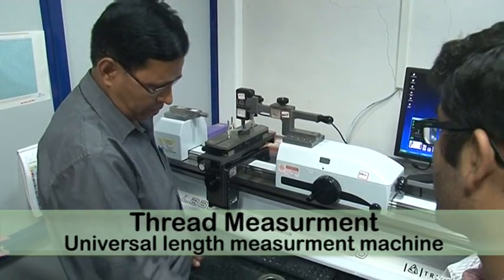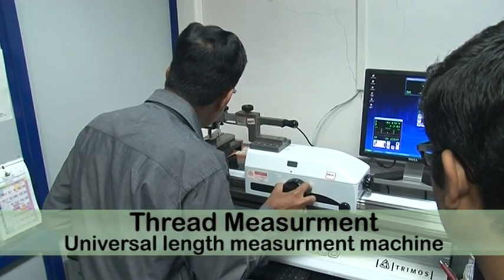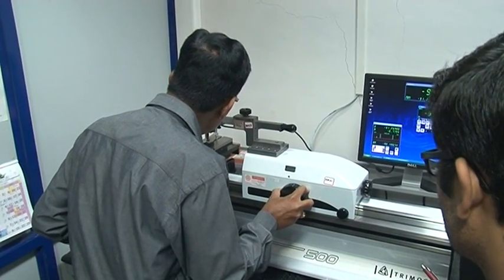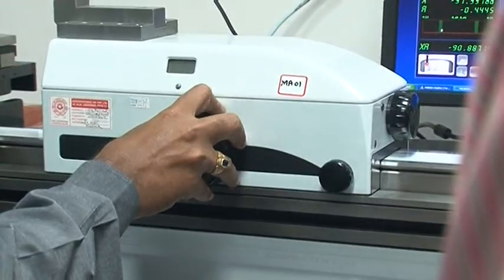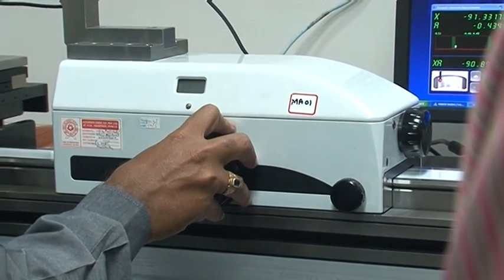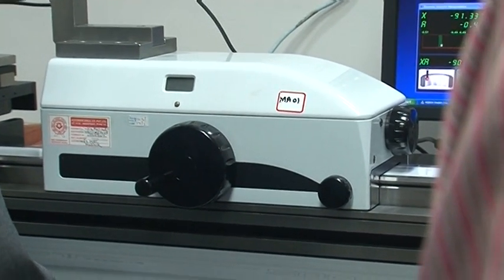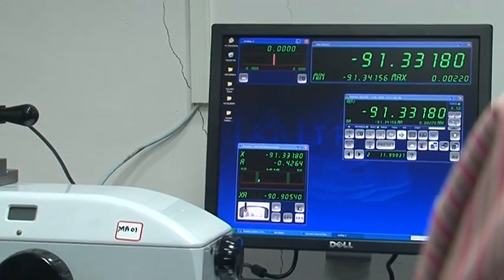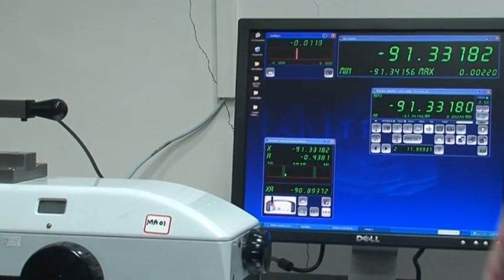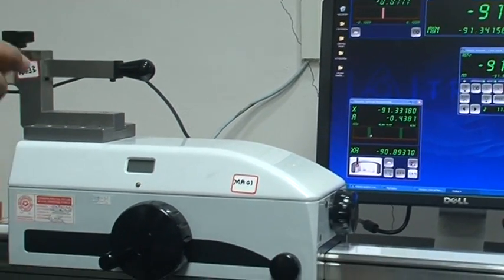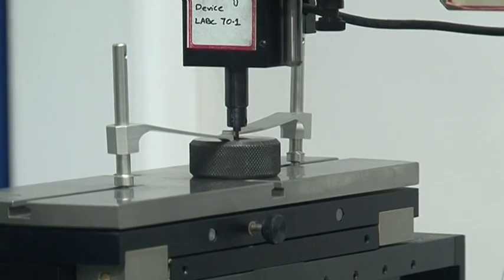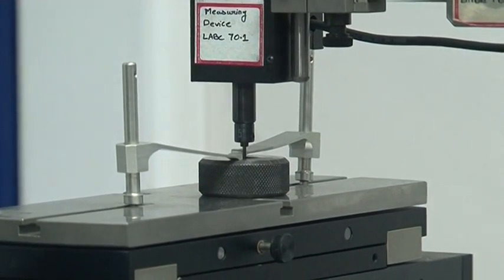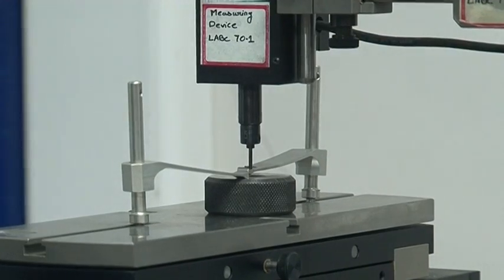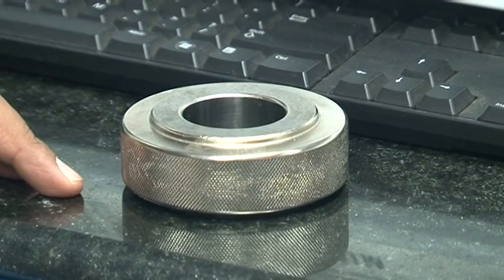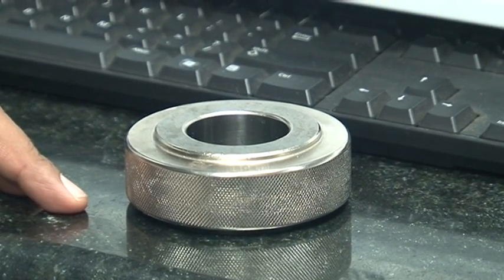Single axis measuring machine. We are using this machine for calibration of inside diameters, outside diameters, length masters, micrometer setting standards, thread plug gauges and thread ring gauges. The range of this instrument is 500 mm with a least count of 0.01 micron. For thread ring gauges we use T-shaped ball probes and for thread plug gauges we use thread measuring wires.